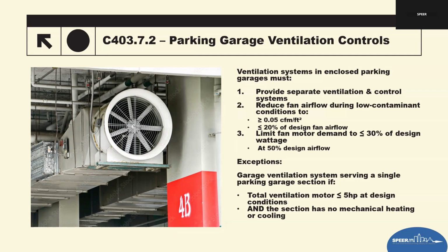So parking garages represent a major opportunity for energy savings. Older garages typically run fans continuously at 100%. The 2024 code now forces the system to have intelligent controls to reduce airflow and energy use while maintaining safety throughout the contamination sensors and proper logic controls.